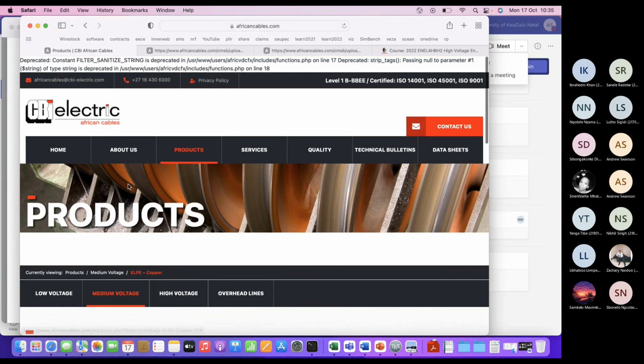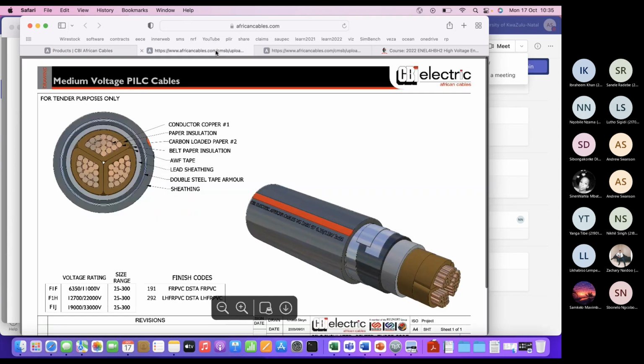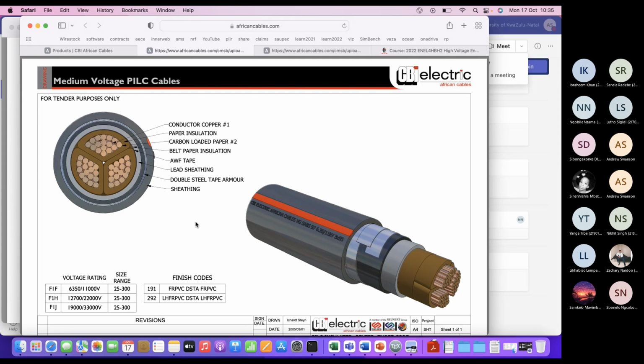Quickly, I went to the CBI Electric African Cables website. And there's an example of a medium voltage PILC cable. When it comes up. Right, so this is a 3-phase cable. You can see your copper conductor. You can see around it, it has paper insulation. Between the copper and paper insulation, it's got carbon loaded paper. Then it's got that for all 3 phases.